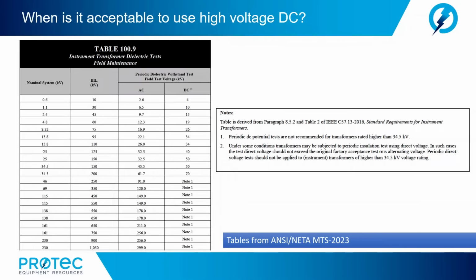All right, now moving on, we also see DC referenced in NETA table 100.9, instrument transformer dielectric test field maintenance. Now, the table is derived from paragraph 8.5.2 and table 2 of the IEEE C57.13 standard requirements for instrument transformers. Now, in the notes, we do see that periodic DC potential tests are not recommended for transformers rated higher than 34.5 kV. So although it does give us an option where DC testing could be acceptable, we do have to take care when looking at instrument transformers, particularly those rated higher than 34.5 kV.